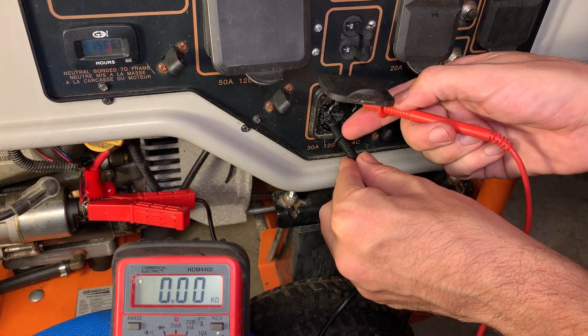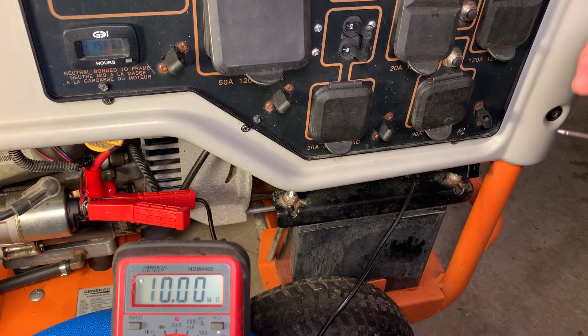Now this is a low voltage test, so it doesn't guarantee anything, but if it was open lead, which on my meter is indicated by a blinking 1, or the resistance was really high, like say above 0.5, then you might have a problem. Actually, you do have a problem, but in this case, it's testing well. Doesn't mean it is well, but it's not bad. So let's move on to the power head. Yeah, these screws are already loose. So someone's already had a look.